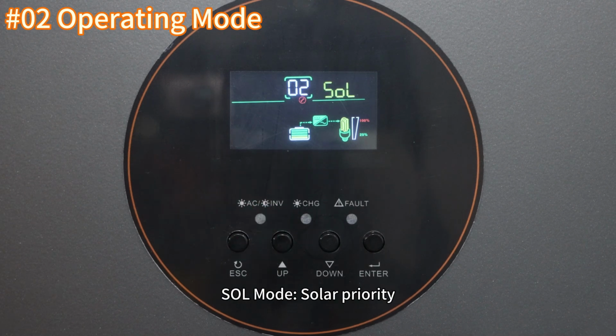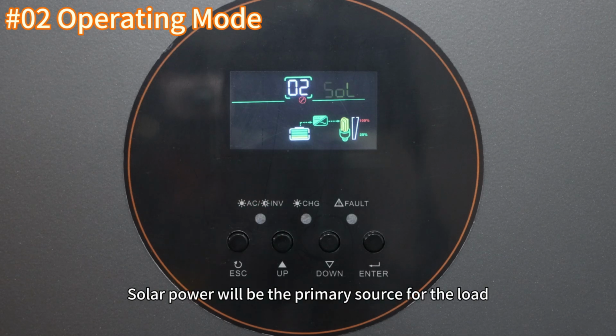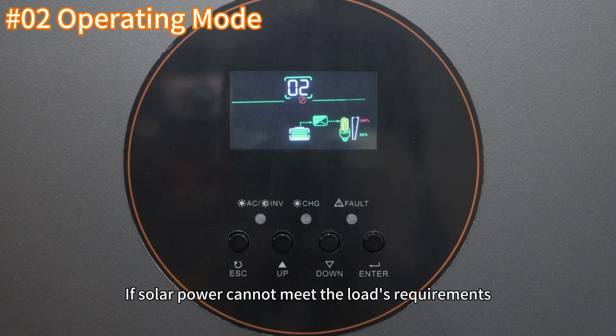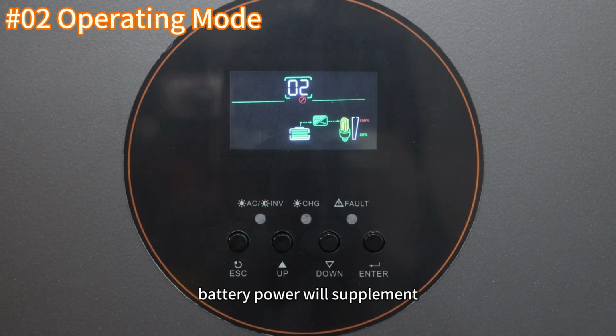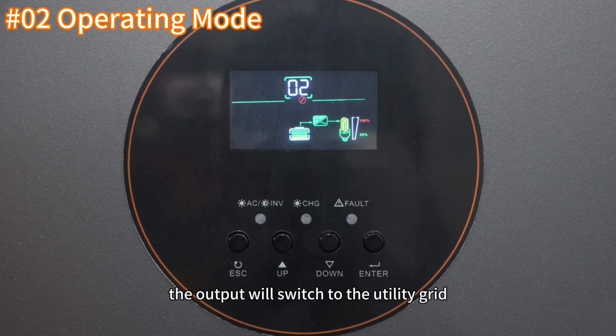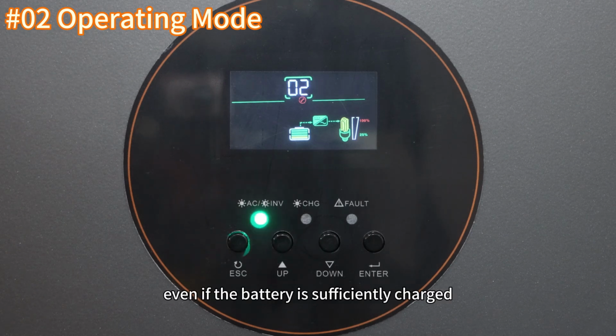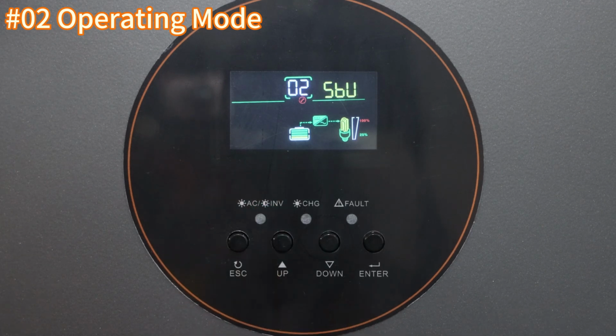SOL mode, solar priority. Solar power will be the primary source for the load. If solar power cannot meet the load's requirements, battery power will supplement. When the solar power is unavailable, the output will switch to the utility grid, even if the battery is sufficiently charged.